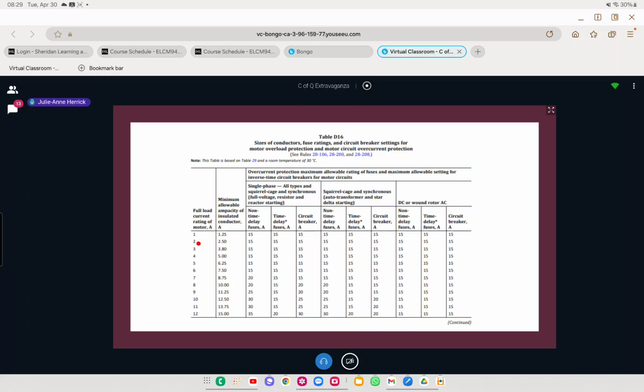So if you notice, for continuous duty, we all know continuous duty is 125%. Well, that's like right here. If you have a full load current rating of 1 amp and it's continuous duty, you multiply that by 125%, you end up with the allowable ampacity of 1.25. So this already does that for you as well. It takes your FLA, continuous duty is right here. So an FLA of 12 amps, continuous duty, is actually 15 amps, and then you go to your table 13. So you don't have to do any math. D16, Appendix D. There you go.